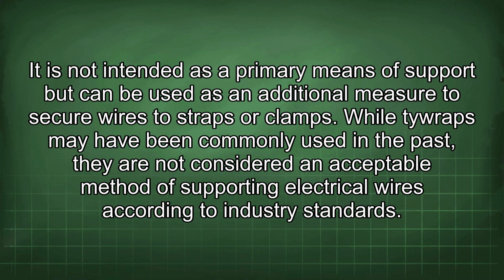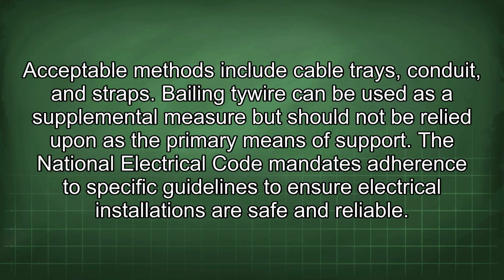While Tywraps may have been commonly used in the past, they are not considered an acceptable method of supporting electrical wires according to industry standards. Acceptable methods include cable trays, conduit, and straps. Baling tie wire can be used as a supplemental measure but should not be relied upon as the primary means of support. The National Electrical Code mandates adherence to specific guidelines to ensure electrical installations are safe and reliable.